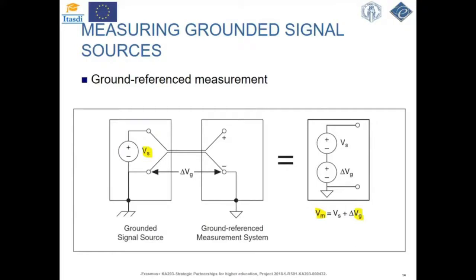This potential difference is generally not at DC level, but rather a noise at the power line frequency. Also, the loop between the signal and the system's ground introduces DC and AC noise and worsens the measurements. This is because the potential difference between the two grounds causes a ground loop, and the ground loop introduces a current to flow between the grounds of the circuit. On the other hand, we can still use a ground referenced system if the signal voltage levels are high and the interconnection wiring between the source and the measurement device has low impedance. In this case, the signal voltage measurement is degraded by the ground loop, but the degradation may be tolerable.